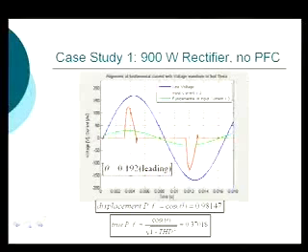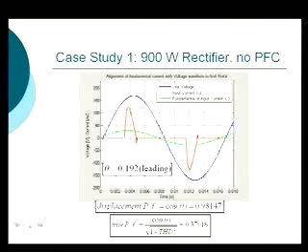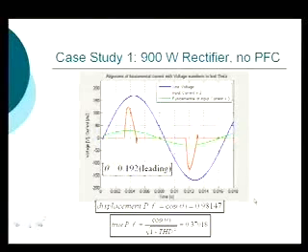Next we need to calculate the displacement power factor. You look at the phase of just the fundamental, because the fundamental is what provides the real work — the harmonics can't produce any real work. We see an angle of about 0.2 radians, and it's leading, as you'd expect with a capacitive load. The displacement power factor alone gives a pretty good power factor of 0.98.